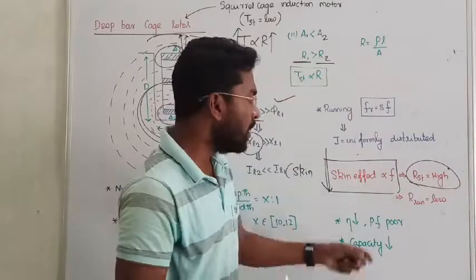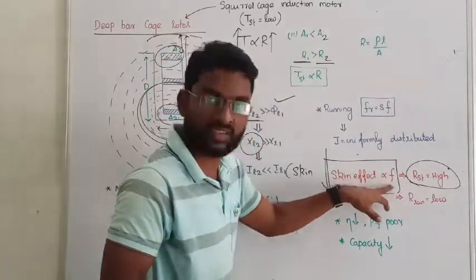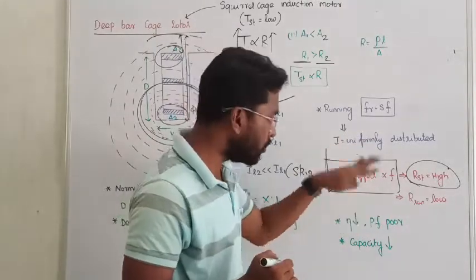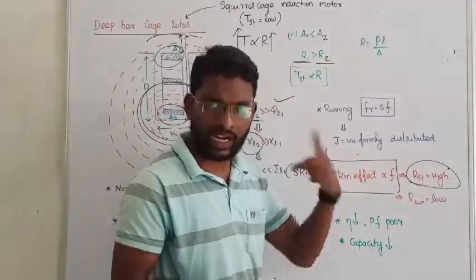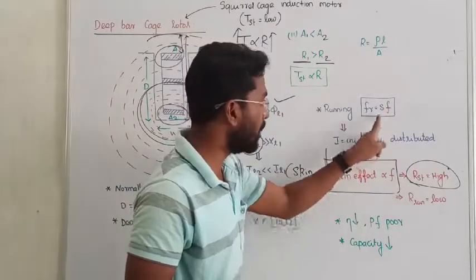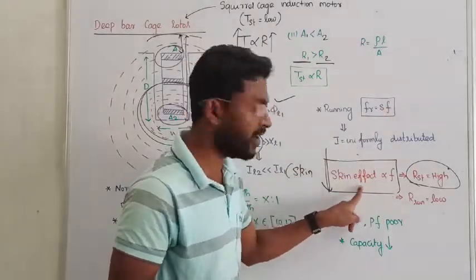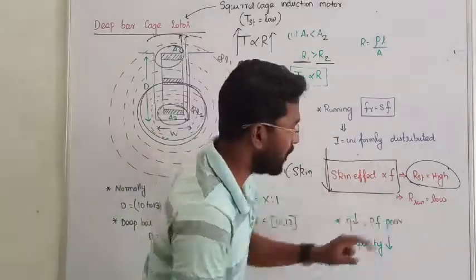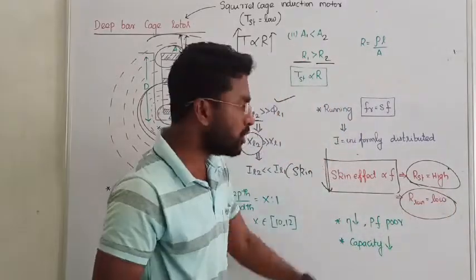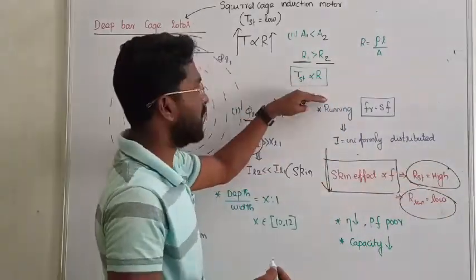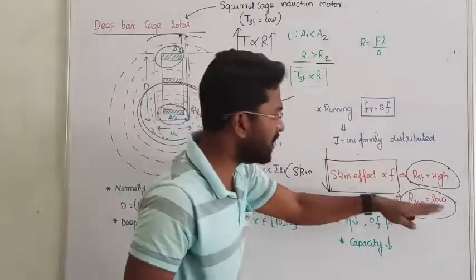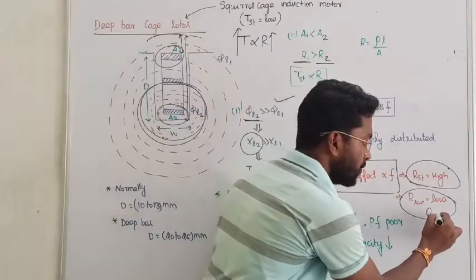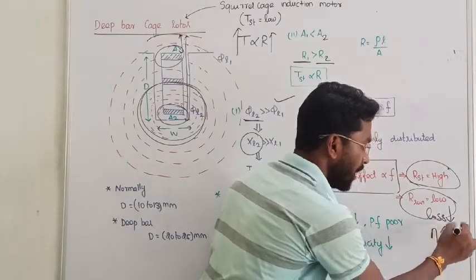Frequency is high, current contribution is less. Running condition, rotor frequency is less, skin effect is less, current is evenly distributed, resistance is less. Starting resistance is more, high starting torque developed. Running condition resistance is less, efficiency is improved.